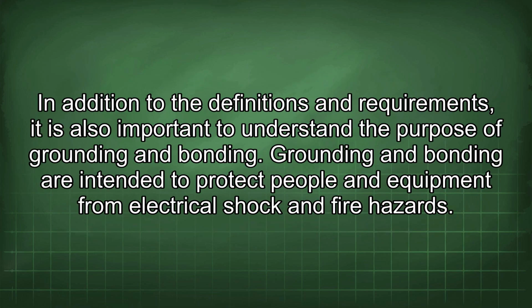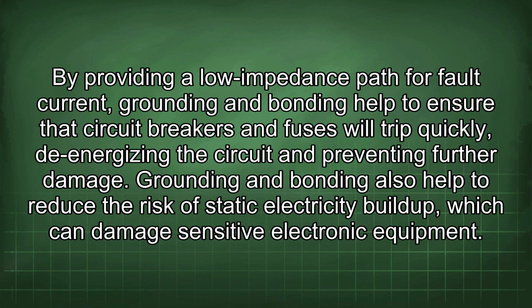In addition to the definitions and requirements, it is also important to understand the purpose of grounding and bonding. Grounding and bonding are intended to protect people and equipment from electrical shock and fire hazards. By providing a low impedance path for fault current, grounding and bonding help to ensure that circuit breakers and fuses will trip quickly, de-energizing the circuit and preventing further damage. Grounding and bonding also help to reduce the risk of static electricity buildup, which can damage sensitive electronic equipment.